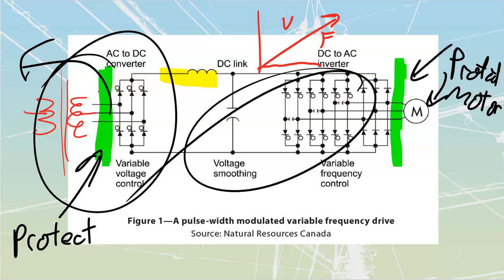A lot of drives, by the way, do have built-in reactors. If you're not sure what to do, if you don't want to spend hours trying to sort out what the proper size is, buy a VFD that has a built-in reactor. There's loads of them out there. The manufacturers put them in there because they are sick of dealing with burnt-out VFDs and complaints about motor warranties. So they've started to build these things with the reactors as a component. You can buy them separately without the reactors, or with the reactors. When in doubt, filter it out. If you don't know whether it's going to be a problem, err on the side that it might be a problem, and just make sure you get rid of it.